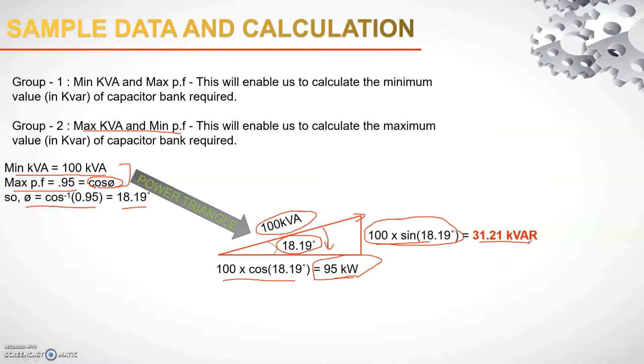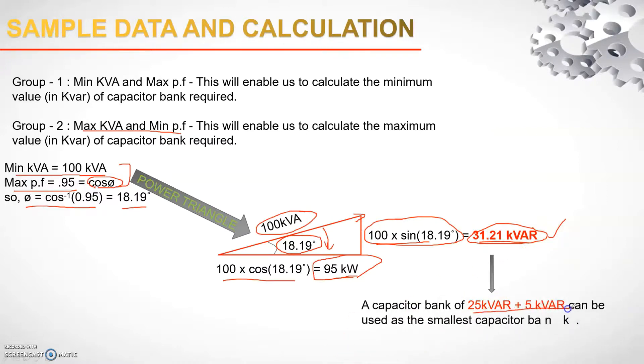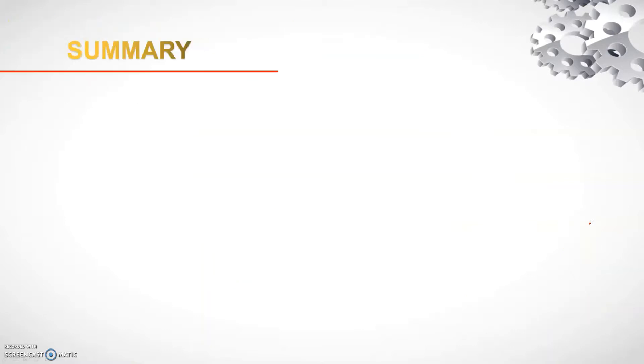At minimum kVA and maximum power factor, 31.21 KVAR is the least amount of reactive power to compensate. We select a capacitor bank close to but slightly less than this value. Using standard sizes, we connect a 25 KVAR bank plus a 5 KVAR bank in parallel on one channel of the reactive power manager, giving 30 KVAR — sufficient for minimum load power factor compensation.